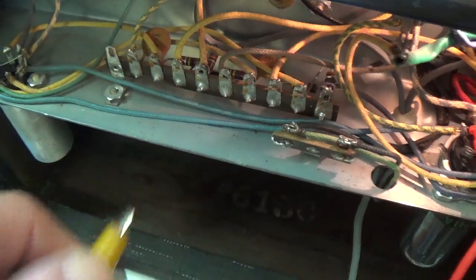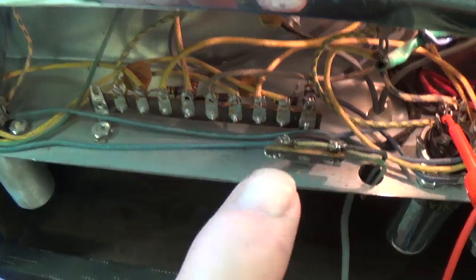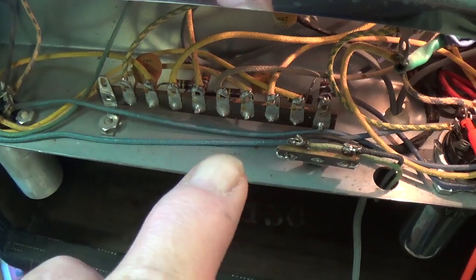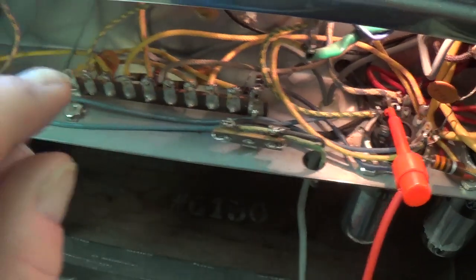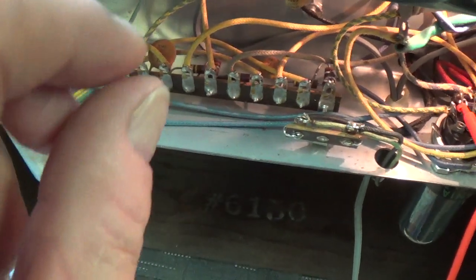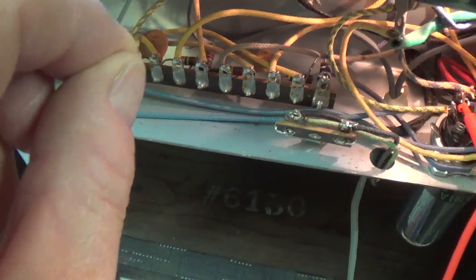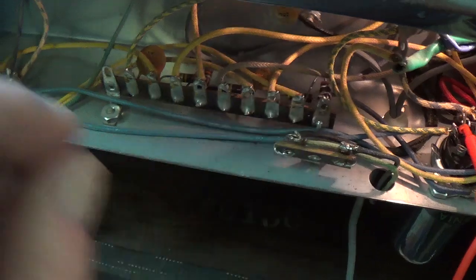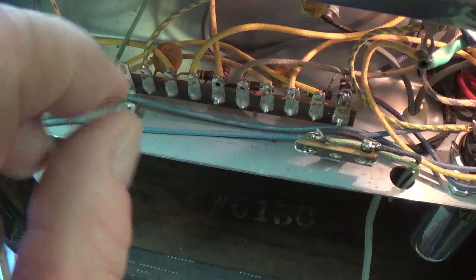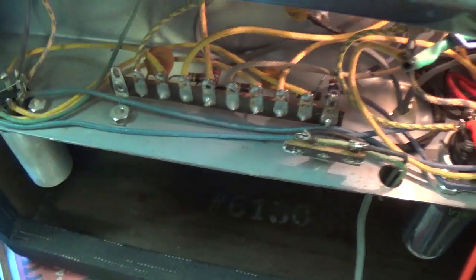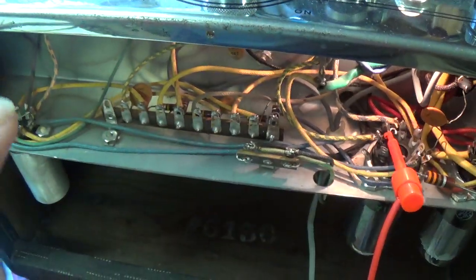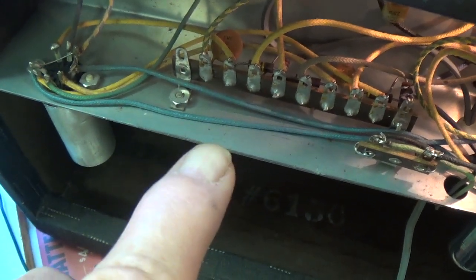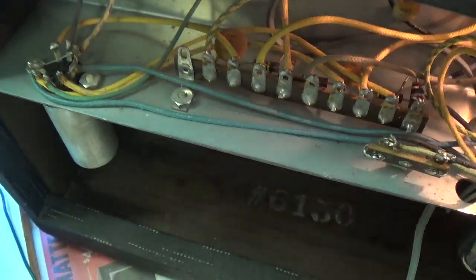Now, if you're willing to let the chassis float and use a 2-wire cord to connect this circuit, you can go in with your oscilloscope ground lead and connect any place in the chassis without a concern. Okay, and once you've connected, we know then concern begins. You can't touch metal, and if you hook another oscilloscope ground clip up, it has to be to exactly the same spot. But you have much greater safety and freedom of choice if you do not ground the chassis of the device that you are testing.